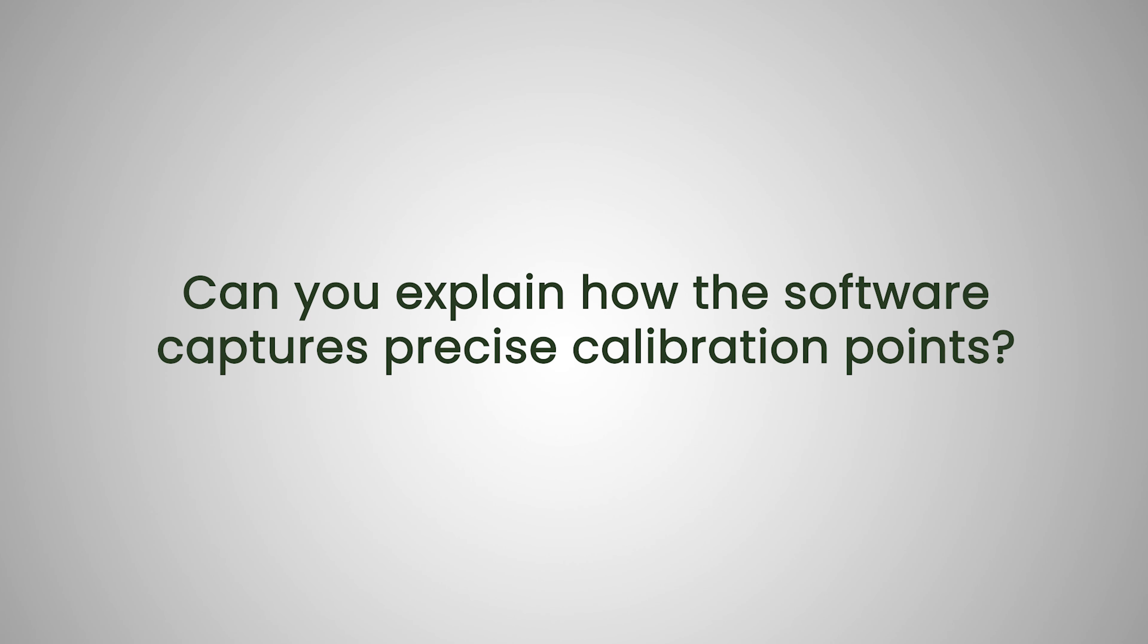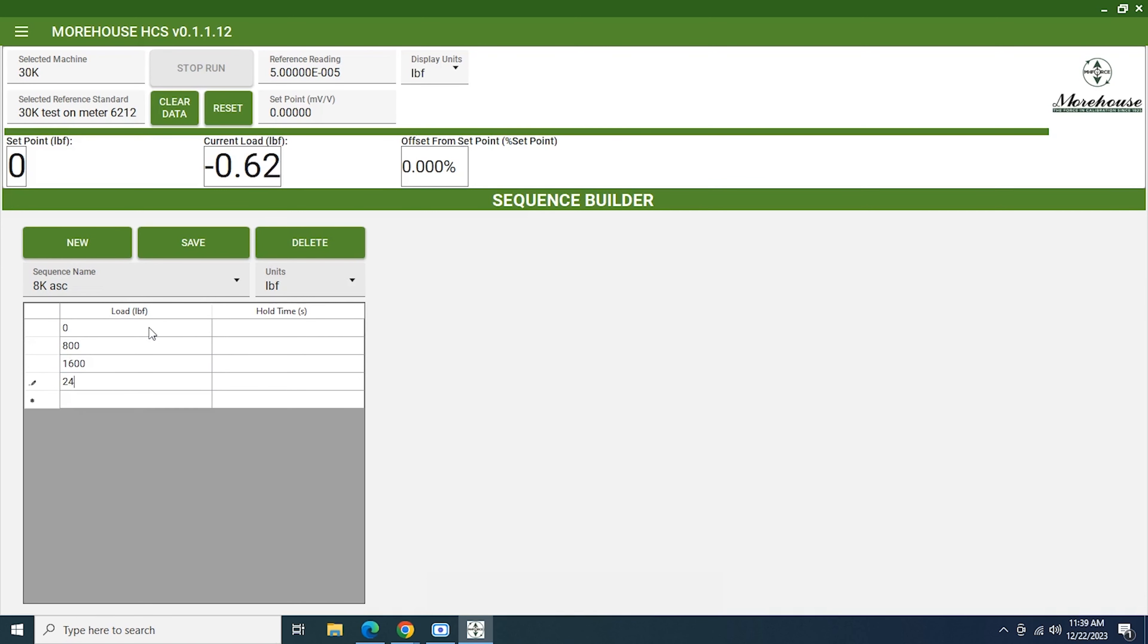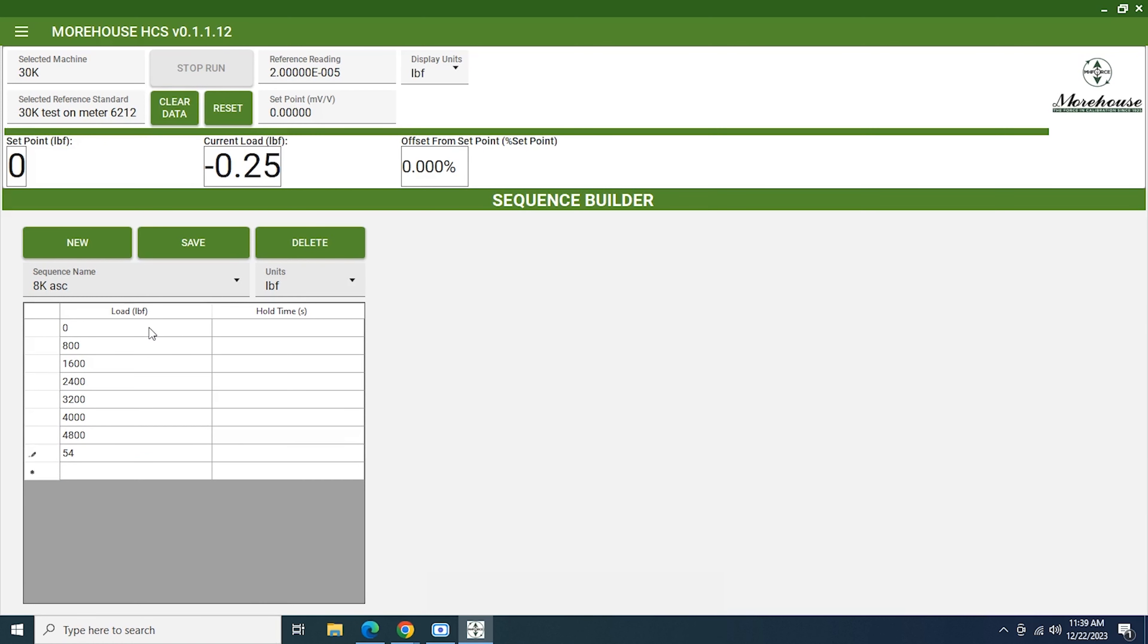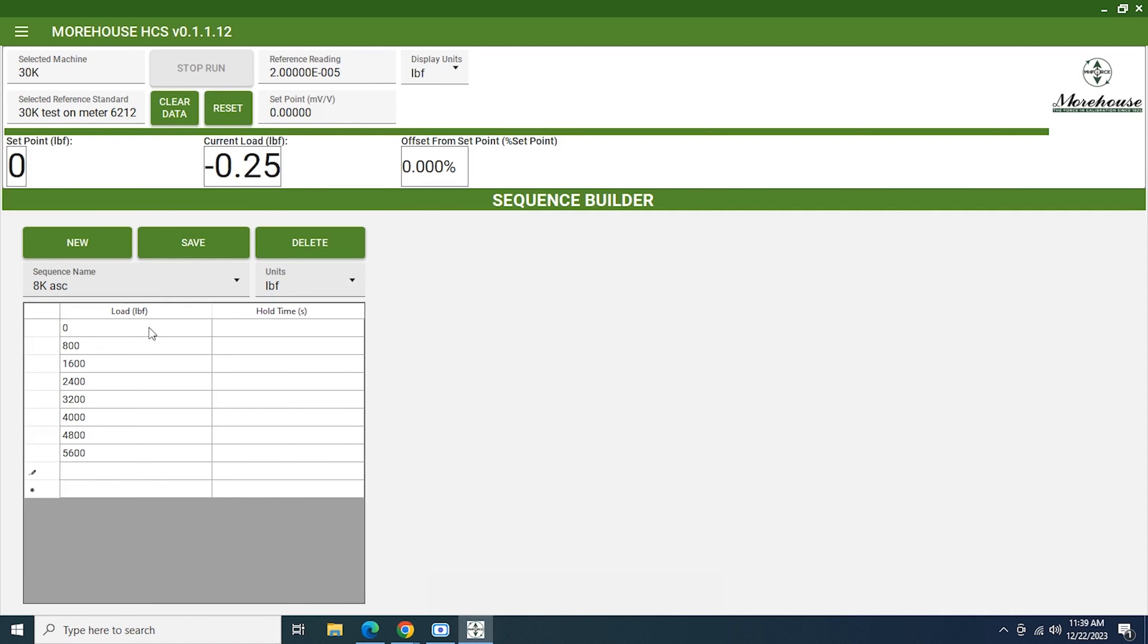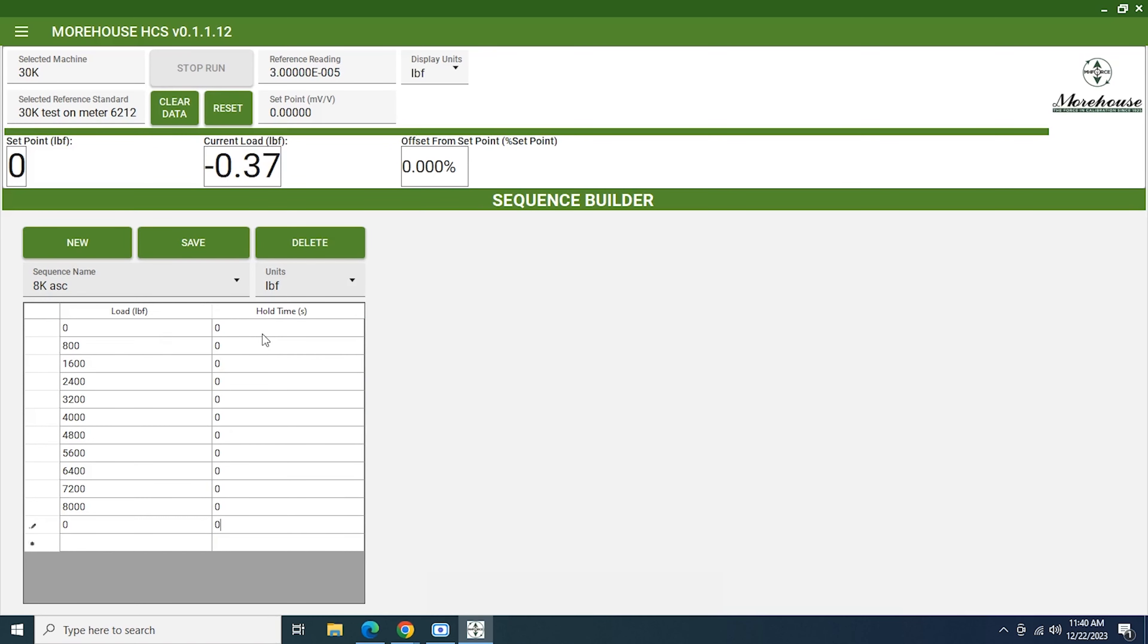Can you explain how the software captures precise calibration points? Yes, so you can build a load sequence with as many load points as you want in it for it to get readings at. And it will grab as many readings from the indicator during that time as you would like and average those numbers together and report them. So I can do that at each sequence, at each load point. So if you wanted to take a hundred load points or a thousand you can do that and at each of those points take as many readings as you'd like.